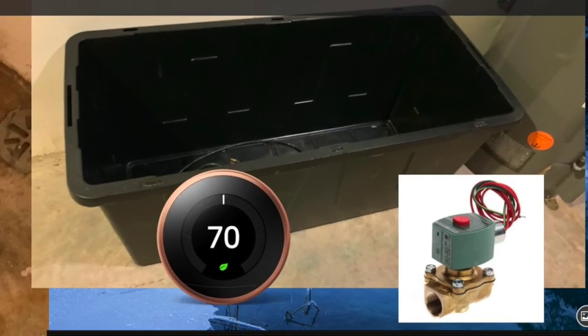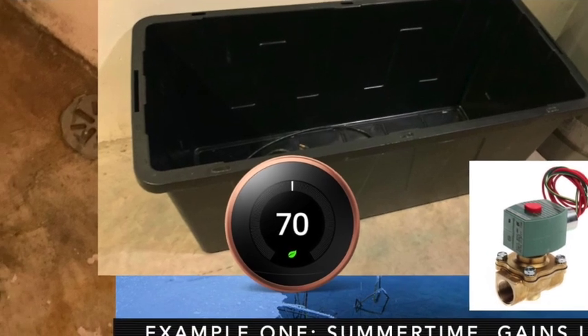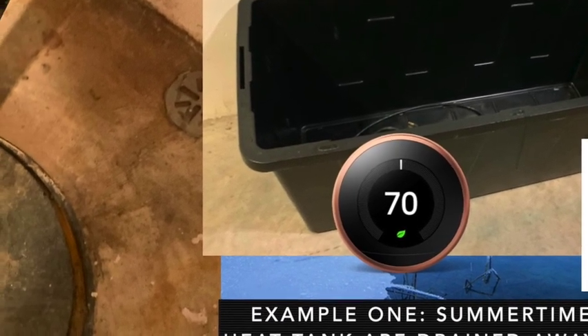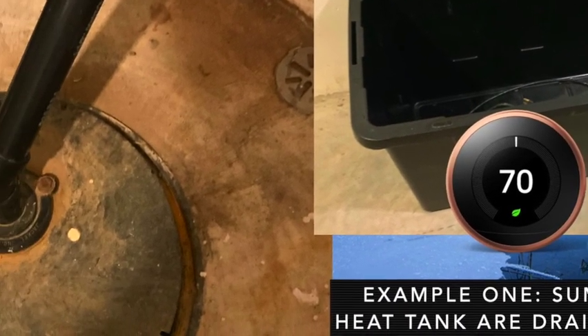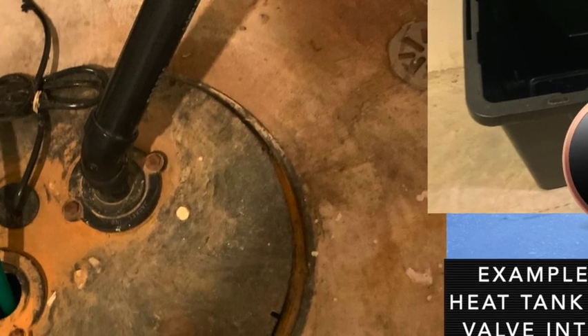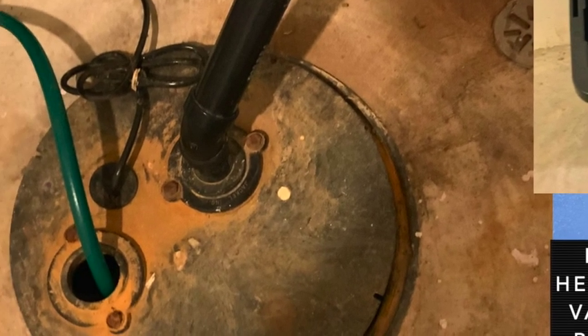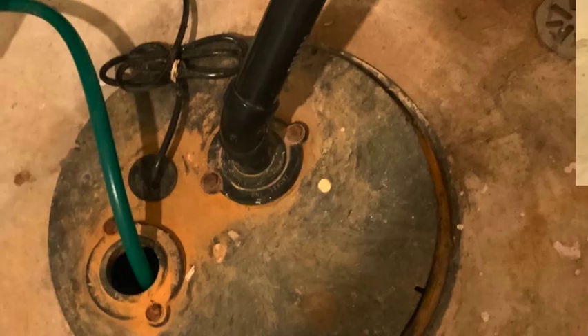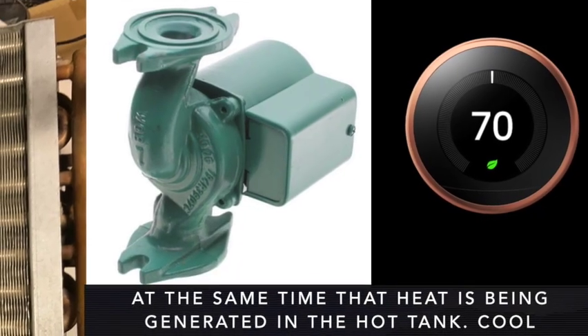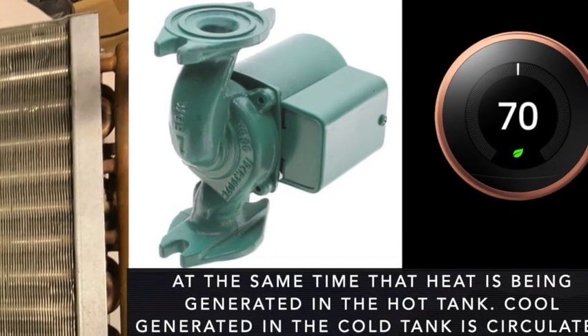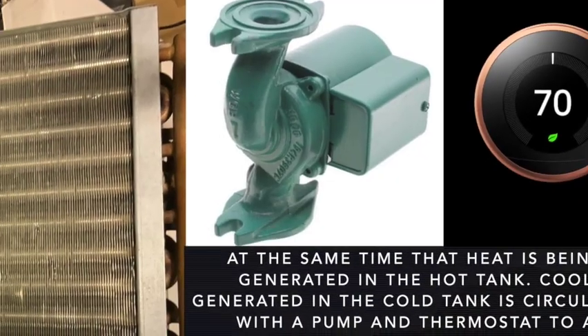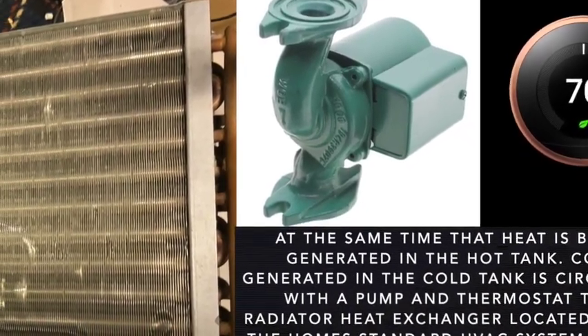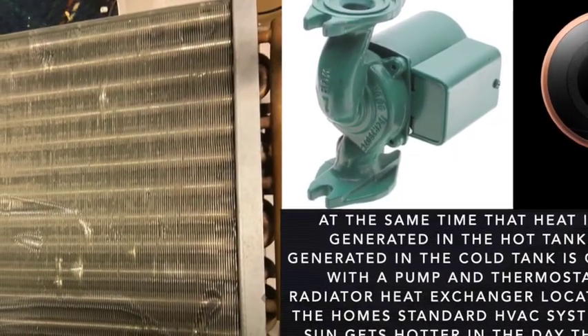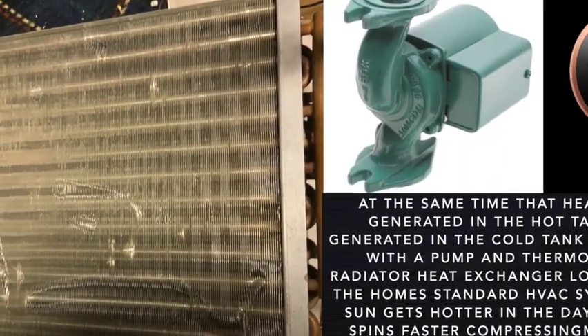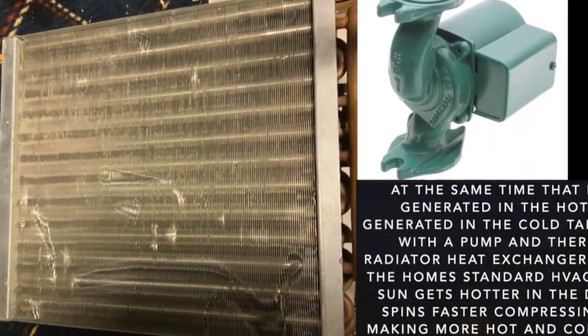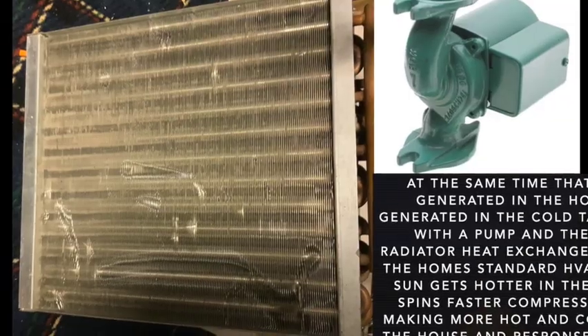The hot tank will then be refilled with sump water, well water, lake water, or any other available water source as the cooling source for the solar heat pump module. At the same time the heat is being generated in the hot tank, cool generated in the cold tank is circulated with a pump and a thermostat to a radiator heat exchanger located within the home's standard HVAC system.